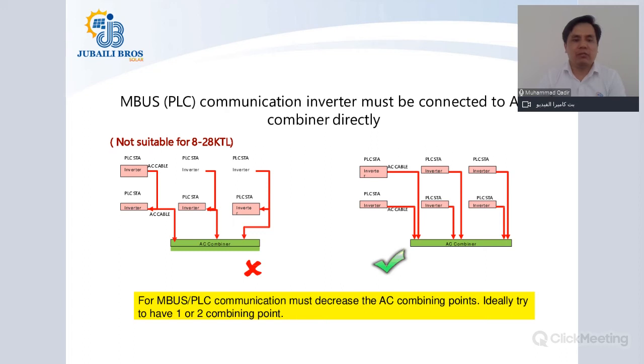For MBUS communication, the inverter must be connected to the AC combiner directly. So for the MBUS, you shouldn't be making too many AC combining points. Make one single combiner, and from that single combiner, take the connection to the smart logger for the smart logger to read your MBUS data. Otherwise, if you're making too many combiners, that can distort the signal of communication.